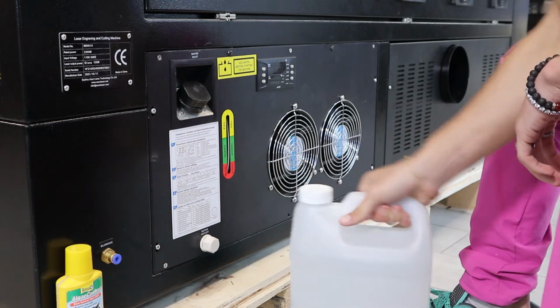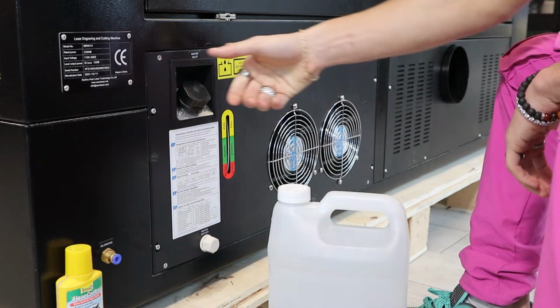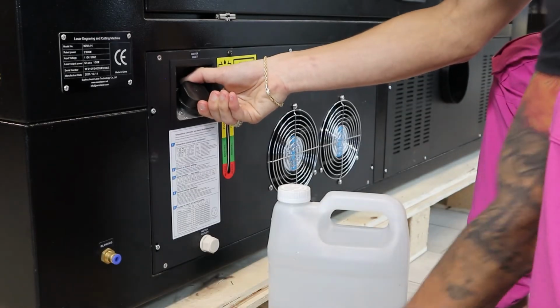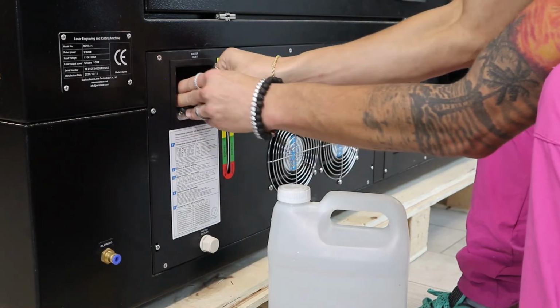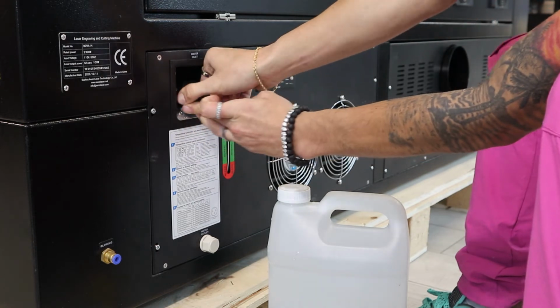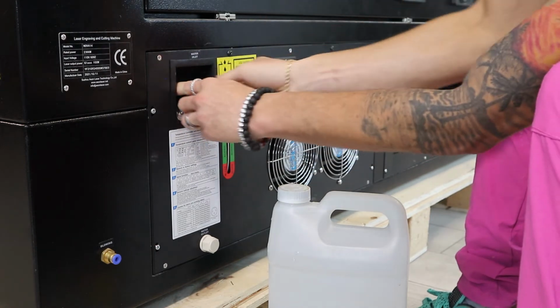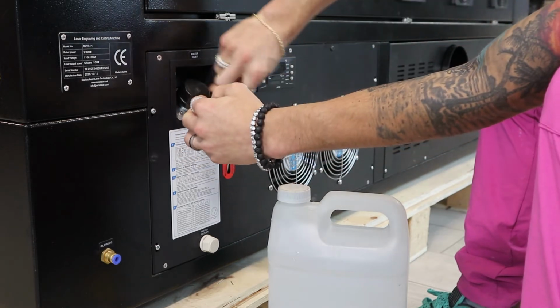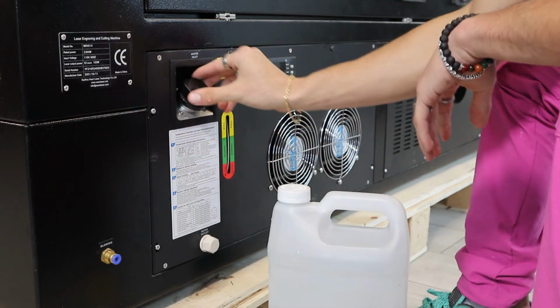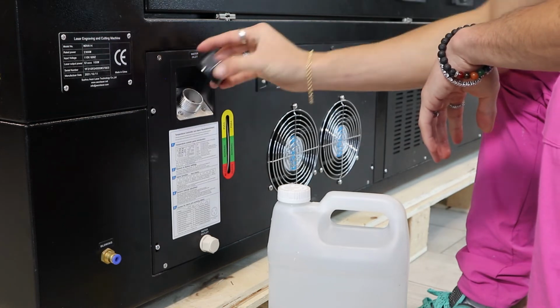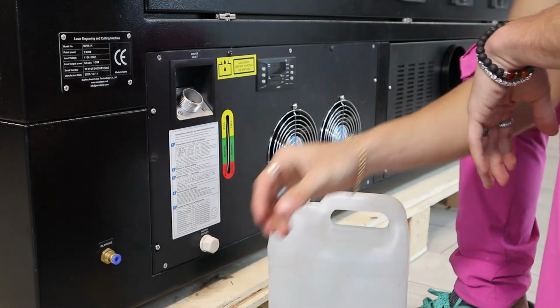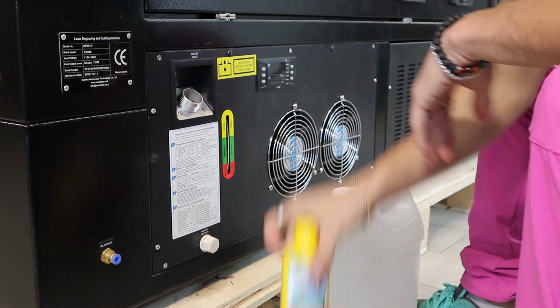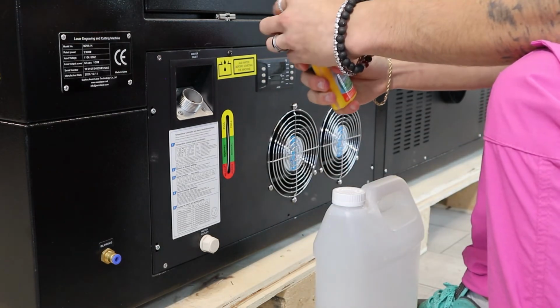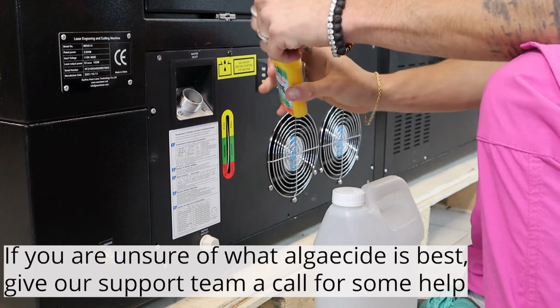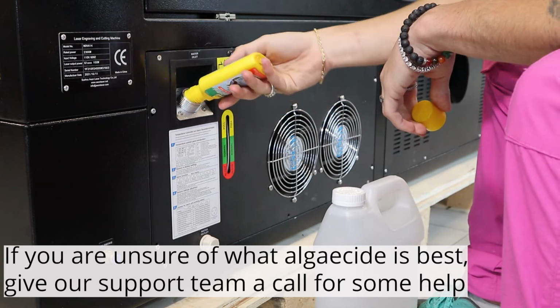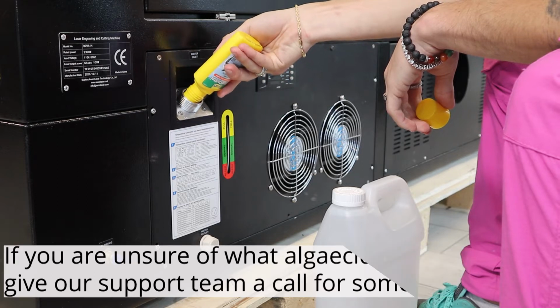Locate your chiller on the back of the machine. Remove the large cap from the water inlet towards the top left of the chiller. We recommend you place some algicide in the chiller as to inhibit algal growth and bacterial growth going forward, keeping the chiller healthier for longer.